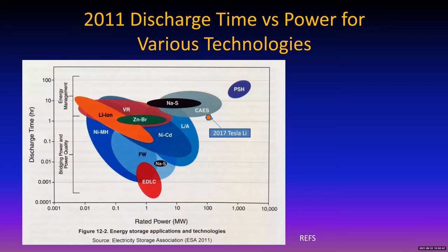It's interesting to compare the 2017 Tesla lithium ion. The curve gives you, depends how many megawatts you want -- this was the existing technologies back then -- and then how fast you want to discharge it. Lithium ions back then, if you want a megawatt of lithium ion power, you had to consider it has to discharge in only about 10 minutes if you want a megawatt. Whereas if you only wanted 10 kilowatts, then you get 10 hours worth with lithium ion technology back in 2011.